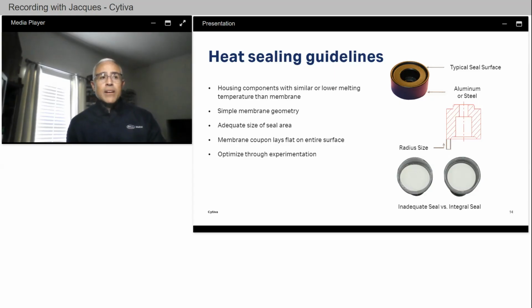The coupon should lay flat on the entire surface when sealing is to occur. Sealing areas that cause the media coupon to dome or wrinkle will not produce a consistent, reliable edge seal. Cycle times with this method should be monitored and not exceed 1.5 to 2 seconds, to avoid damaging the membrane's working filtration area. Also, consider the use of a nonstick coating on the tooling to prevent the edge of the membrane coupon from sticking to the heated tool during use. And finally, the relationship between time, temperature, and pressure for your specific process must be optimized through experimentation.